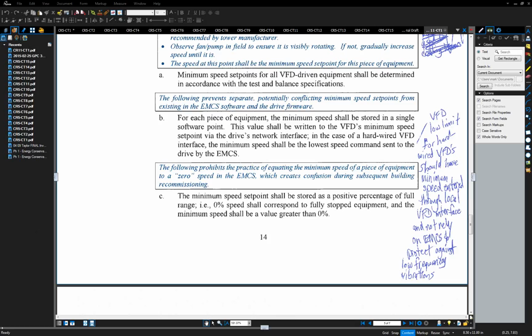Yeah, we have to fight this all the time with owners just because of perceptions out in the marketplace. But anything that's reset by demand has a near cubic curve. So the inlet guide vanes on the variable speed for a centrifugal chiller, for instance, variable speed where you're doing condenser water reset aggressively. For fans, when you're doing supply pressure reset by demand, and also with pumps, where you're doing supply pressure reset by demand, you follow pretty well a pure cubic curve, and you don't end up either in surge nor do you end up having a lot of heat in the motor.